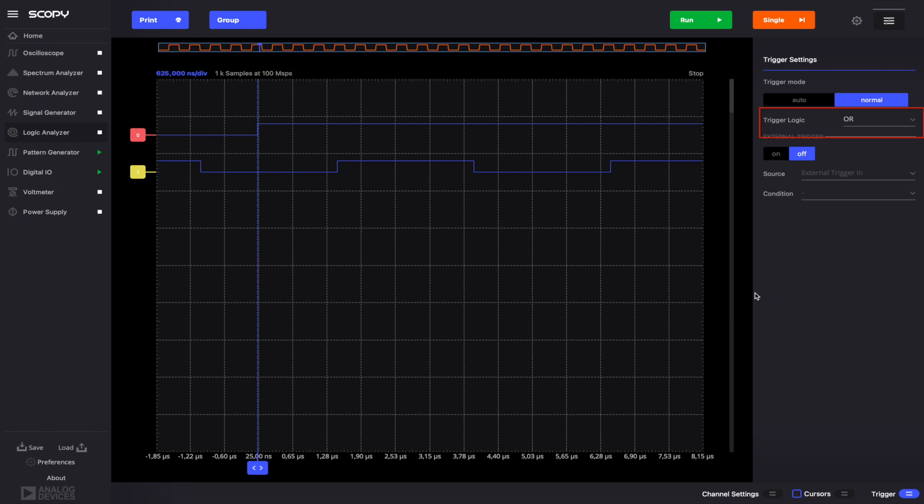In the trigger settings menu, we can also set the trigger logic. The two options, AND or OR, refer to the logic between the external trigger and the internal trigger conditions set on the digital pins. Intuitively, if this option is set to OR, then only one of the trigger conditions needs to be satisfied. On the other hand, when set to AND, the instrument would be triggered only if both the external and the internal trigger conditions were fulfilled. Set the logic to AND.